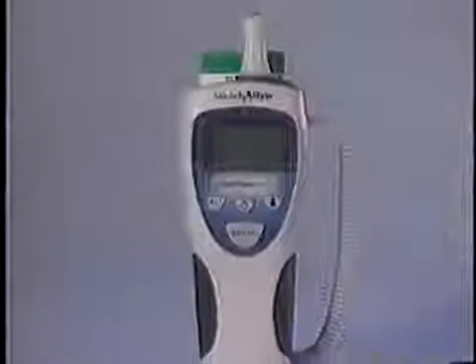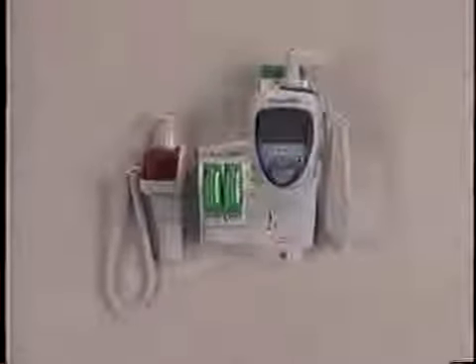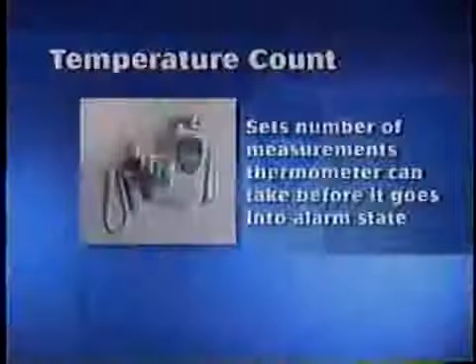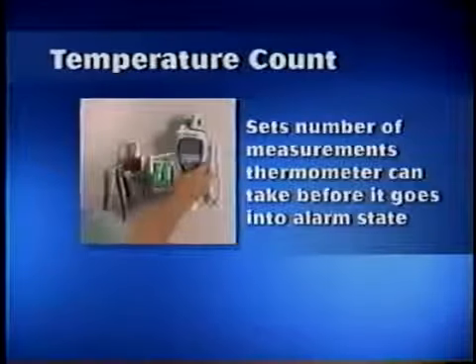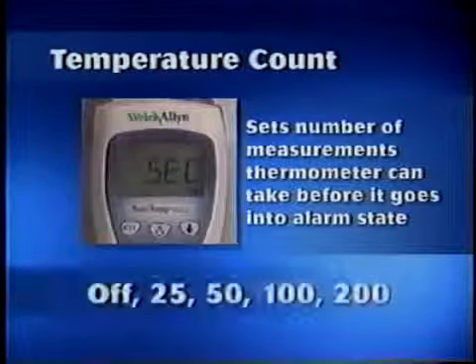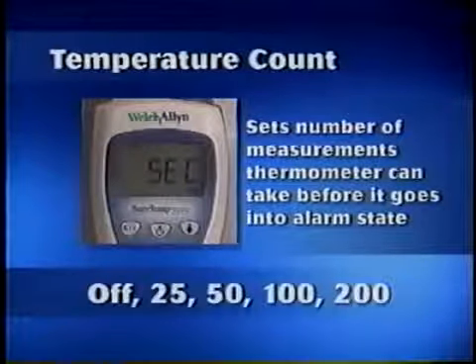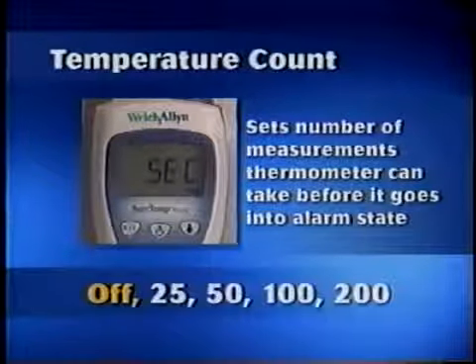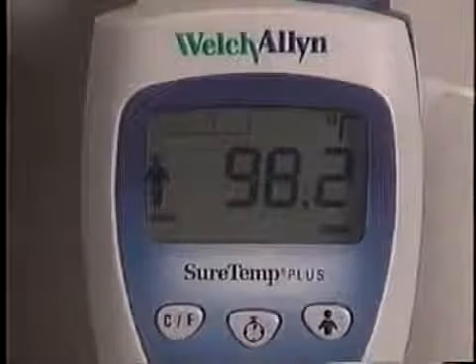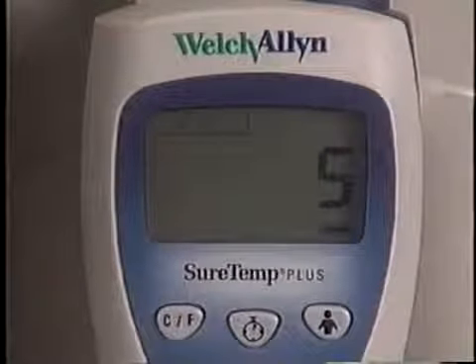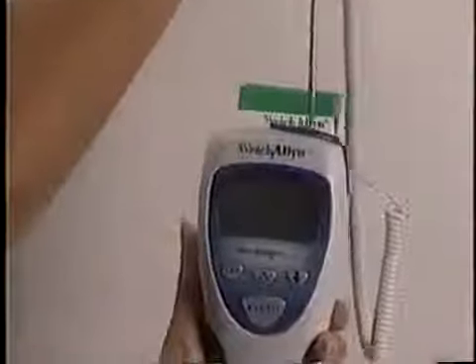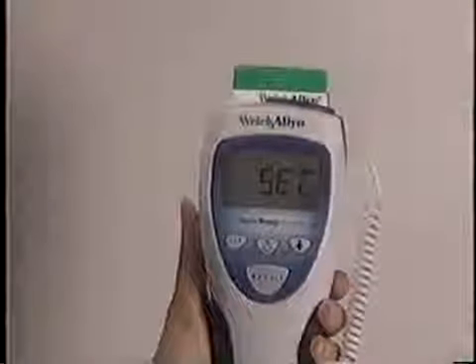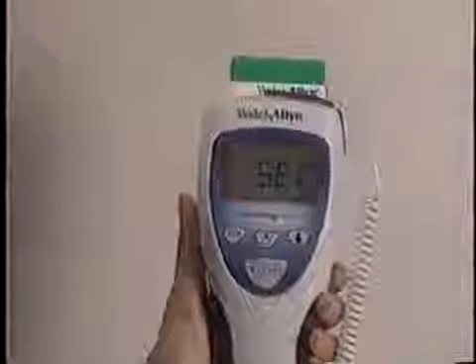This section covers features available only on the Model 692. Your biomedical engineer should refer to the SureTemp Plus service manual to set these features up. Temperature count sets the number of measurements the thermometer can take before it goes into an alarm state. Off, 25, 50, 100, or 200 readings. If the count is set to off, the alarm is disabled. When the thermometer reaches the final 5 allowed readings, it displays SEC along with the number of uses remaining. When the thermometer records the last allowed reading, it beeps for 10 seconds, displays SEC, and is disabled. Return the instrument to the wall holder to reset the security count.